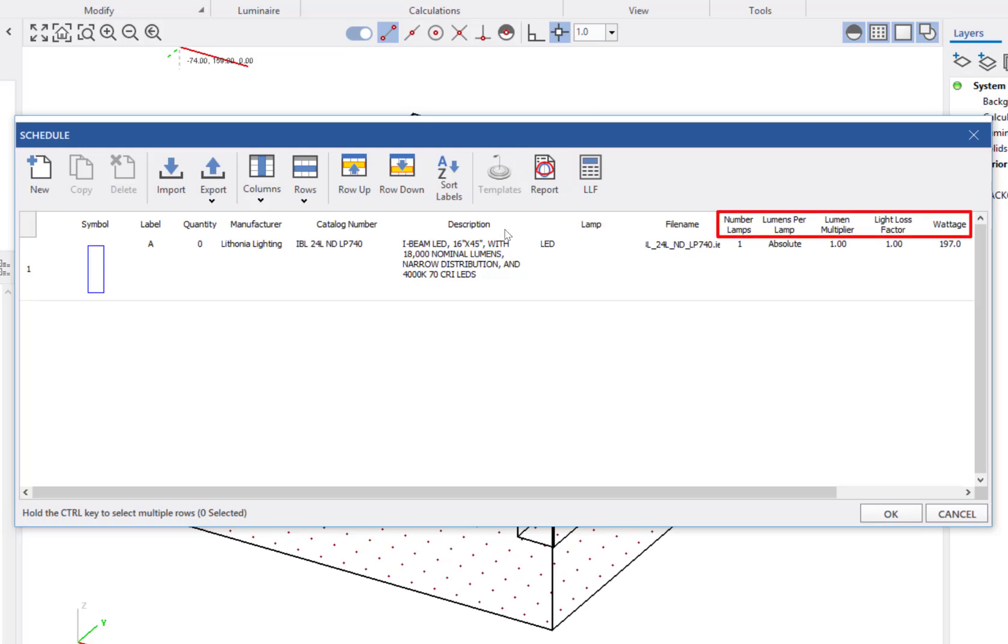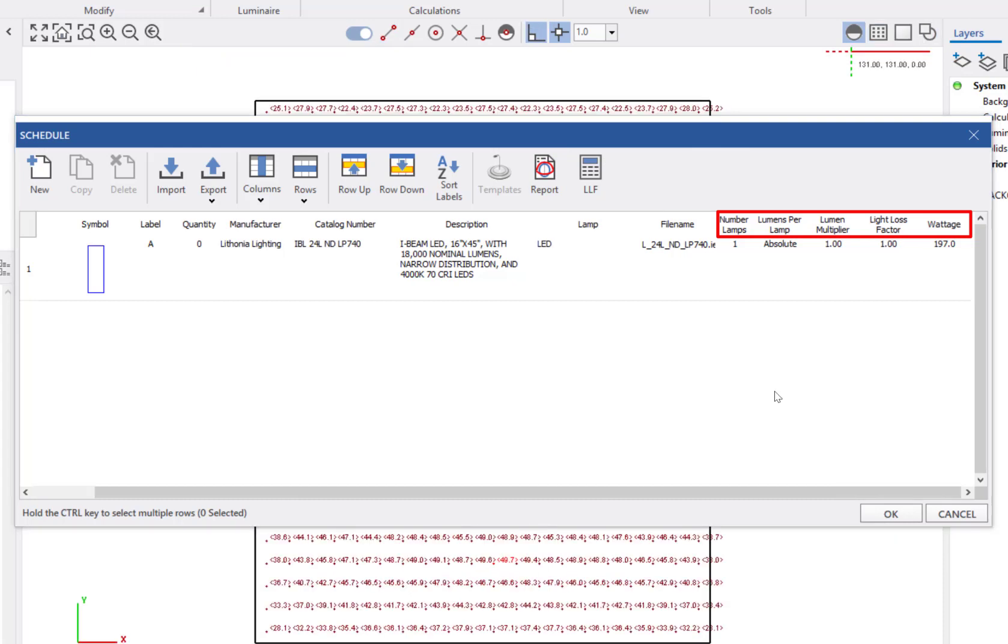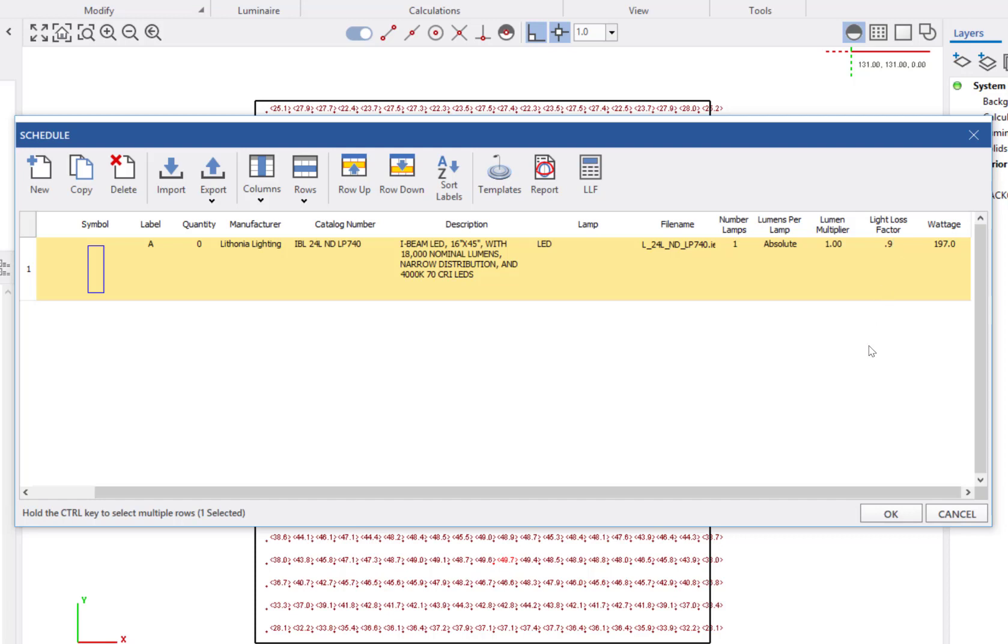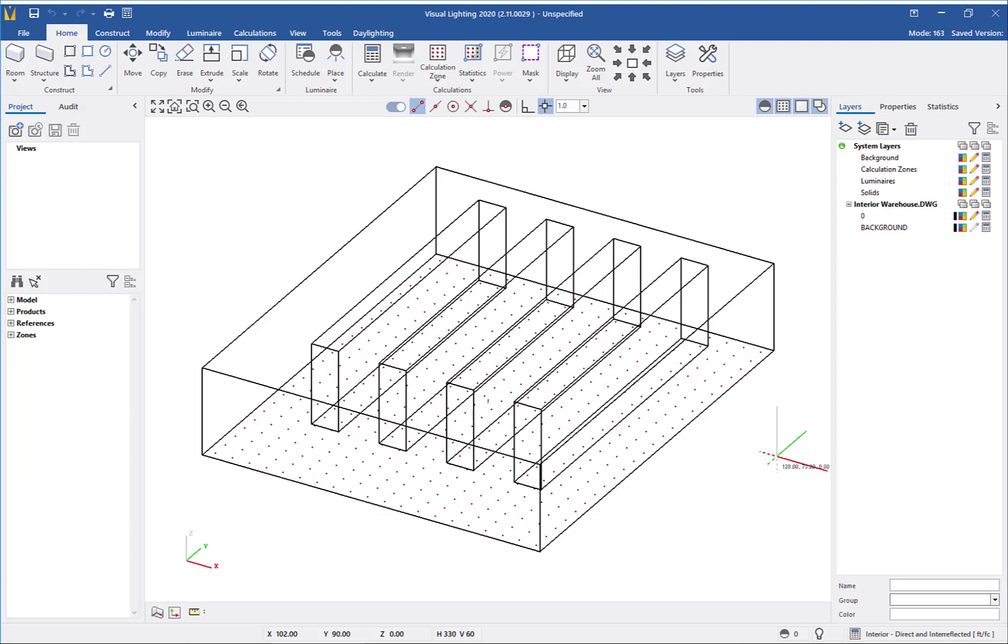From the schedule, I can adjust factors like lumen output on products that are not listed as absolute, the light loss factor, lumen multiplier, number of lamps, and wattage. For this, I will change the light loss factor to 0.9 and leave the other values unchanged.